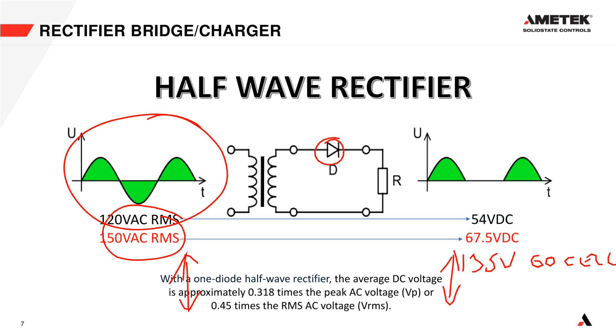As a charger manufacturer, we cannot guarantee what the AC input is going to be. In North America, we stipulate 480 volts, but at this facility here in Stafford, Texas, it usually runs around 500 volts and changes throughout the day - the same happens in most plants. The voltage can change throughout the day, so we need a way to maintain a steady output DC with varying AC inputs. The way we do that is instead of using a diode, we use an SCR.